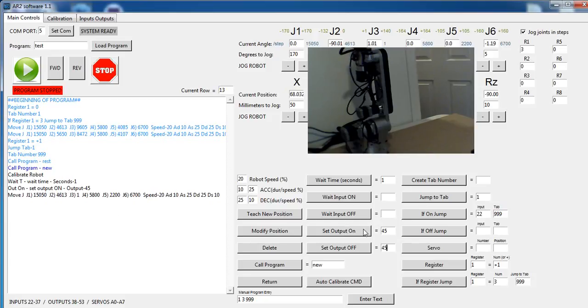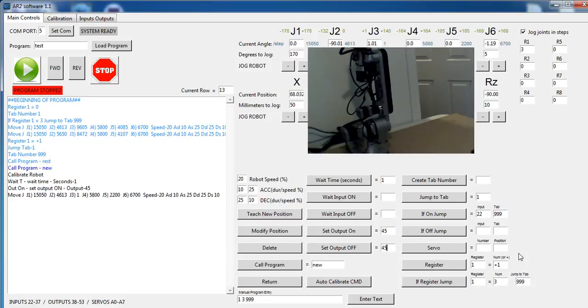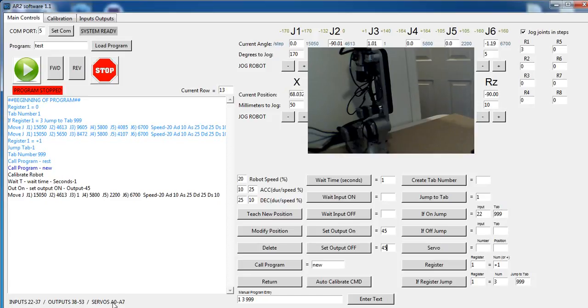So you've got wait times. You can wait for inputs to come on and off, so if you have a condition where one of these inputs is waiting for a machine to finish, or waiting for a fence to close, you can sit and have the program to sit and wait until that happens. Like you said before, you can create tabs, jump to tabs. You can conditionally jump to tabs if inputs are on or off. We can also control servos in the program. Analog outputs zero through seven are set up with a servo module so that you can control servos and run them to positions. And then we already talked about registers and if registers.